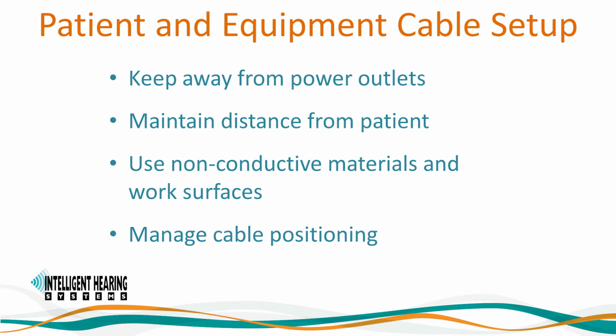When testing a child, position the child's head towards the center of the room, not the wall, especially if there's a system of shafts or conduits for power at the head of the bed. For babies in child seats or being held by a mother, position at least 1 meter from the equipment and the cables. Be prepared to suggest alternative positions for patients in order to obtain good quality EEG. Use blankets and pillows to support the patient's neck. Use non-conductive materials and surfaces across any point where cables, equipment, and patient may touch.